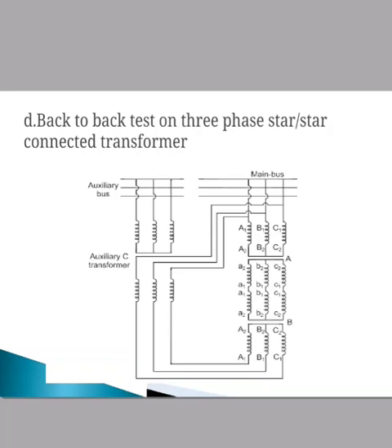to circulate through the primary and secondary of transformers A and B, which is indicated by the ammeter connected in the secondary circuit. The condition is maintained till the final steady state temperature condition is reached. The supply is then switched off and immediately the winding resistance per phase is measured.